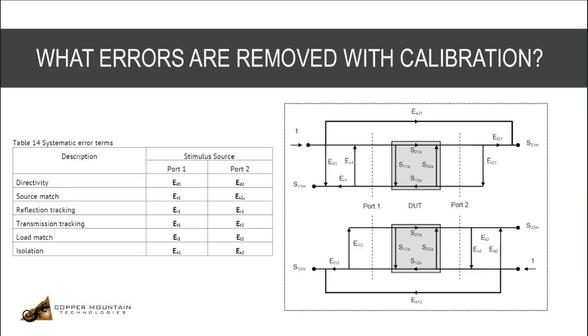At the highest frequencies, smaller mechanical changes will generate larger phase variations. So clearly, when you get into millimeter wave measurement, changes in millimeters or less can cause a couple degrees very quickly.